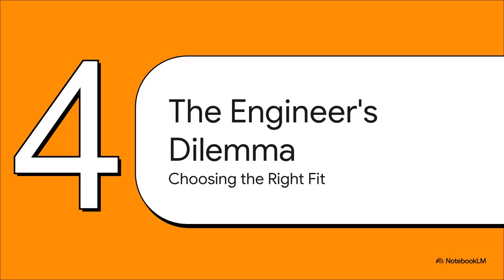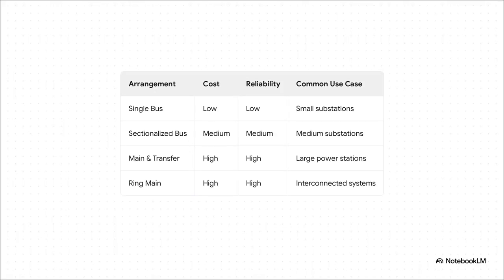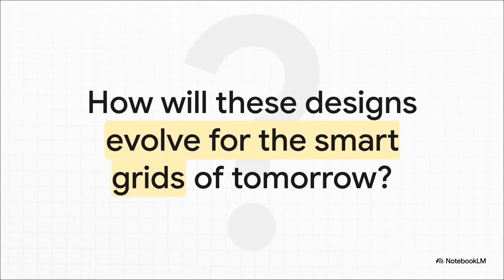So after looking at all these different designs, we come right back to that central challenge, the main dilemma for power system engineers. And this table really sums it all up perfectly. You can see that for a small, non-critical substation, the low cost of a single bus makes a lot of sense. For a medium-sized one, the sectionalized bus gives you a pretty good balance. But when you're talking about large, important power stations or interconnected systems, you really need to invest in those high-reliability systems like the main and transfer or the ring main. In the end, it always comes down to a trade-off between the initial cost and the potential price of a power outage. And that really leaves us with a final thought, doesn't it?